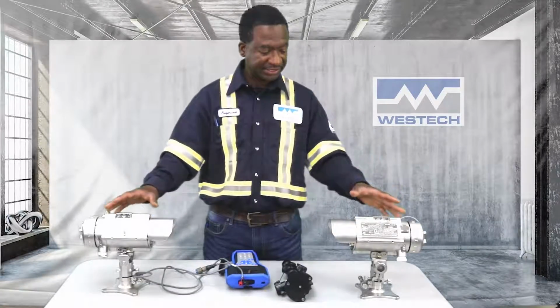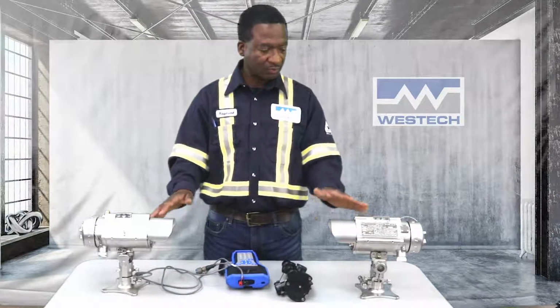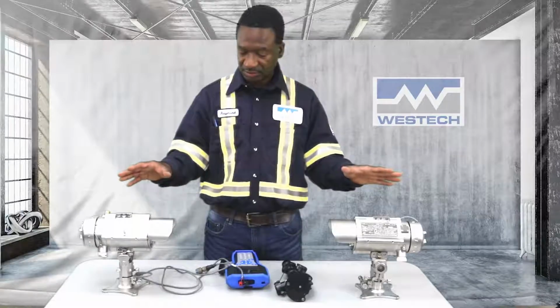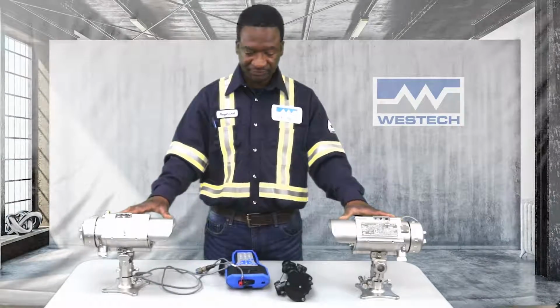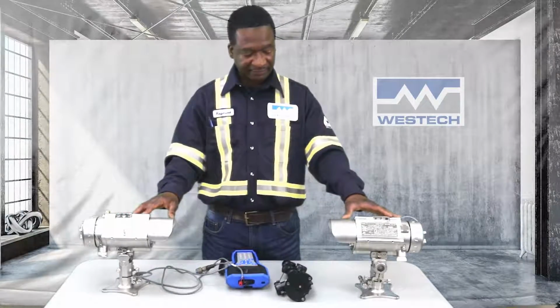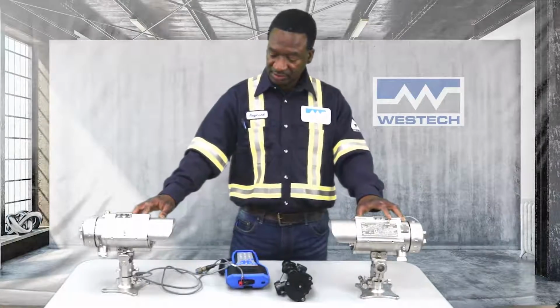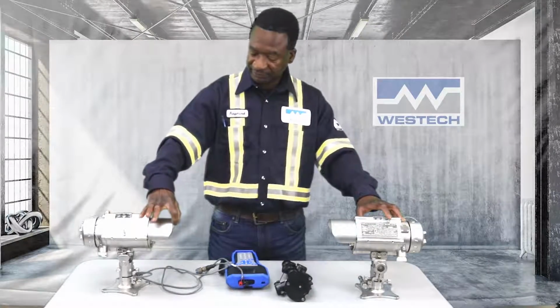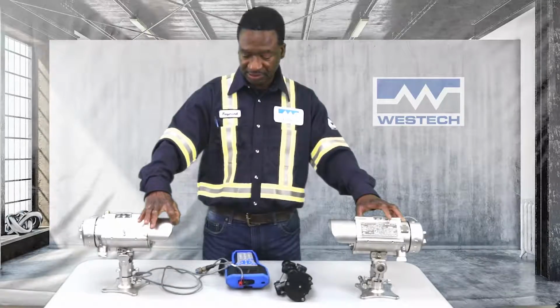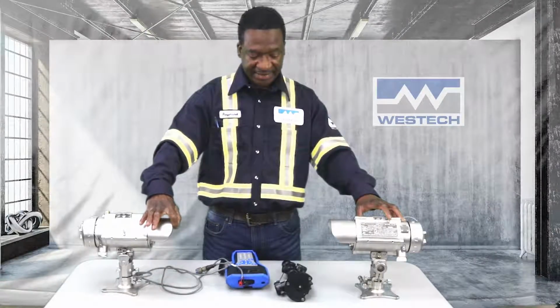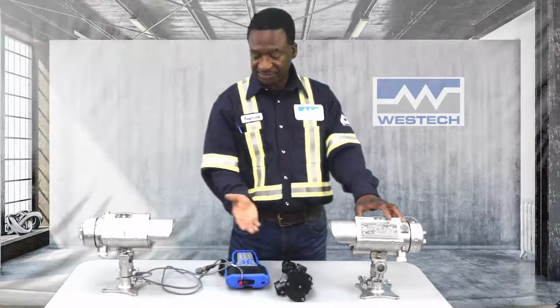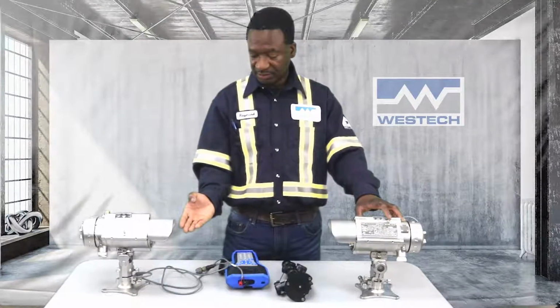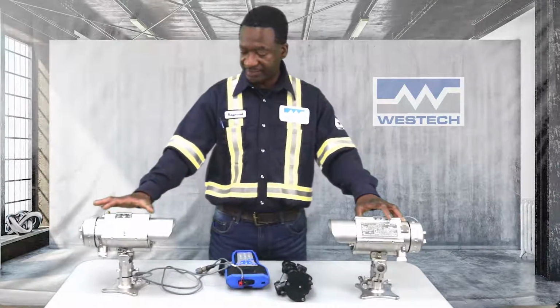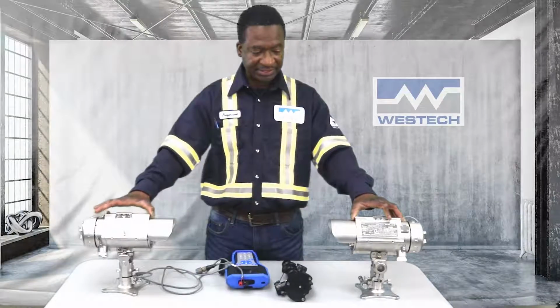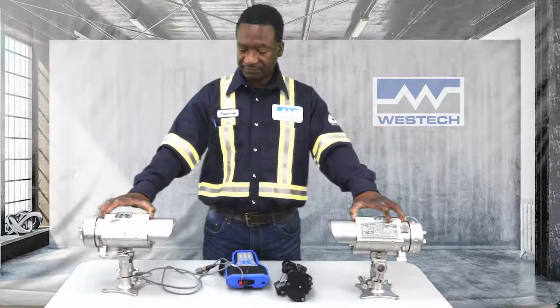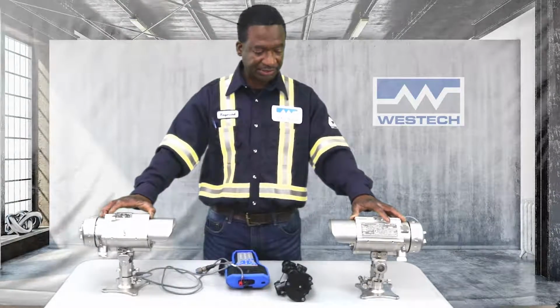In terms of maintenance, once the detection system is installed and the zero calibration is done, you can do a filter response test by fitting specialized filters on the face of the receiver, and the transmitted beam is projected through the filter, and the receiver picks it up, and this is a simulation of gas concentration.